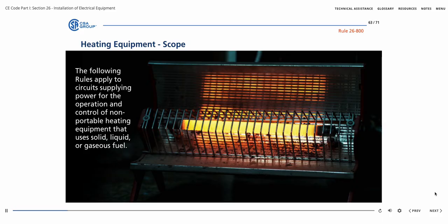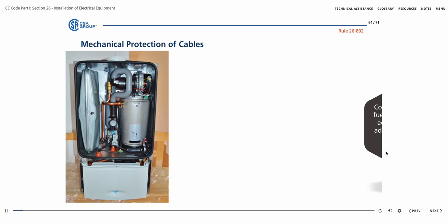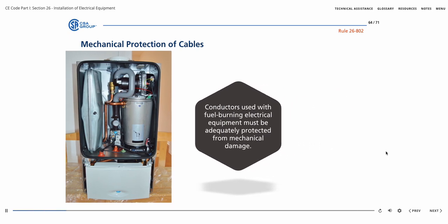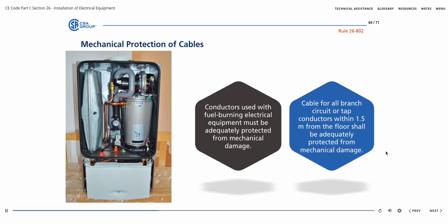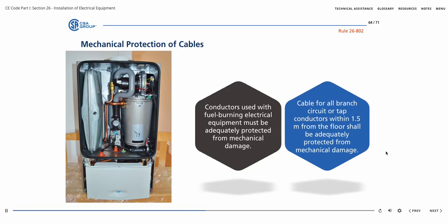Rules 26-802 to 26-808 apply to circuits supplying power for the operation and control of non-portable heating equipment that uses solid, liquid, or gaseous fuel. Conductors used with fuel-burning electrical equipment must be adequately protected from mechanical damage. Rule 26-802 requires cable for all branch circuits or tap conductors within 1.5 meters from the floor to be adequately protected from mechanical damage.